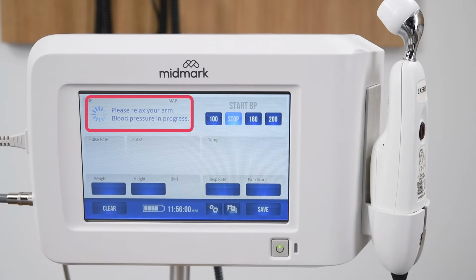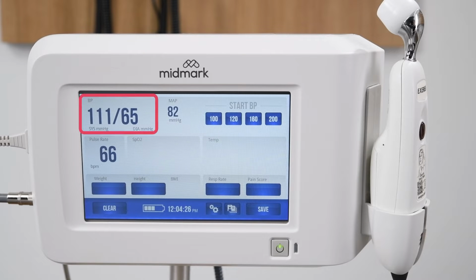During a blood pressure or any other measurement, the clear button is disabled. When the blood pressure measurement is complete, the systolic and diastolic values appear on the screen. A pulse rate will be displayed when a blood pressure measurement is complete. The pulse rate will appear below pulse rate on the screen. The clear button will be enabled when the measurement is complete.